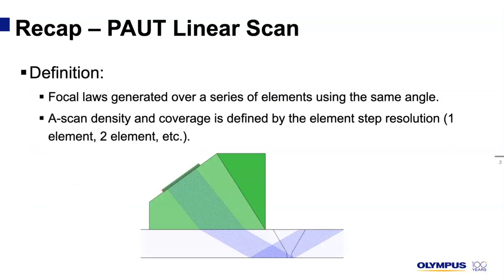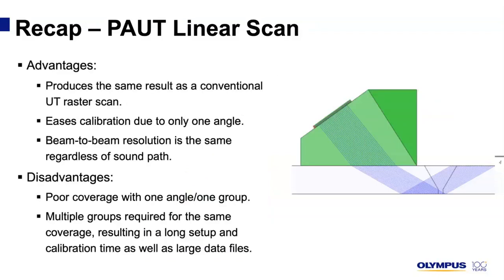First of all, Phased Array linear scan. Basically, you have focal laws generated over a series of elements using the same angle, and the A-scan density and coverage is defined by the element step resolution. One aperture generating one focal law, then we move on to a different aperture generating another focal law with the same angle altogether. The advantages of a linear scan: it produces the same results as a conventional UT raster scan without the need of moving the probe in and out from the weld. It eases the calibration due to only producing one angle. The beam resolution is also the same regardless of sound path as all focal laws are parallel.